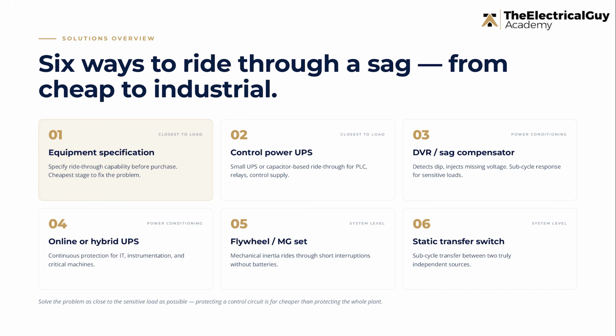The sixth solution is a static transfer switch or fast transfer switch. If a facility has two independent power sources, a transfer switch can shift the load from one source to another when a disturbance is detected. A conventional transfer may take more time. A fast transfer switch can transfer in a few cycles. A static transfer switch, using power electronics, can transfer even faster.